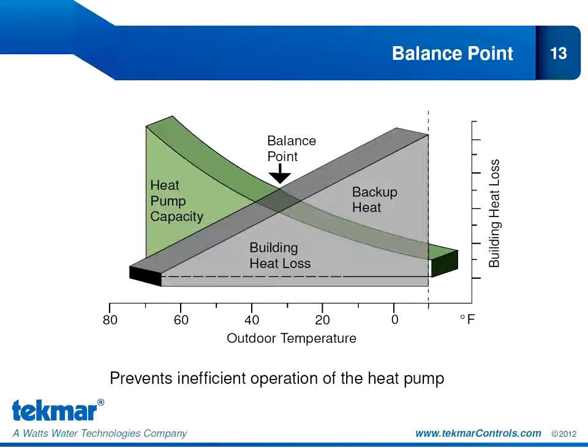Now, balance point is not a fixed setting in the 557. It depends on the capacity of your heat pump, and it depends on your building envelope. So it's very particular to your system. Typically, though, it's in the range of 27 to 35 degrees Fahrenheit. So this balance point setting will prevent the inefficient operation of your air source heat pump.